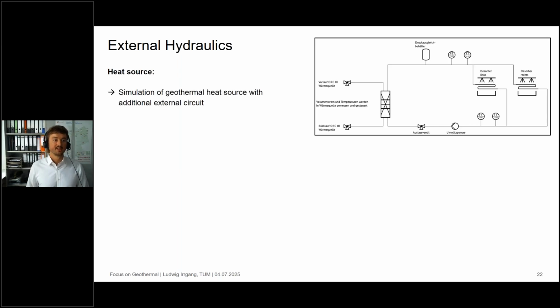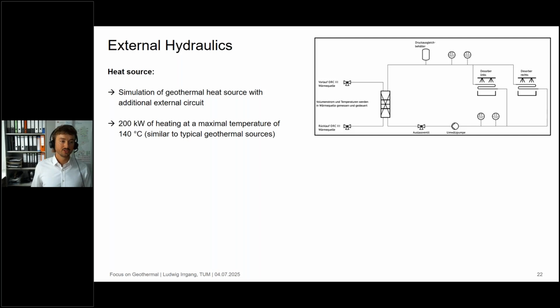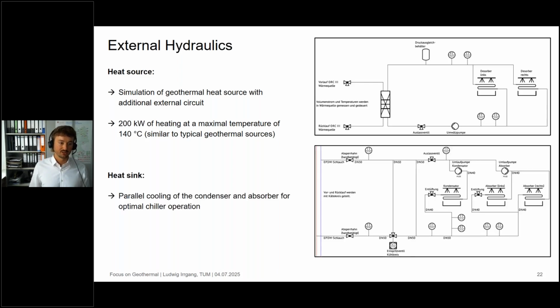For the external hydraulics, we simulate the geothermal heat source with an additional external circuit. So we have the heat source and then another circuit. This way we want to simulate different desorber temperatures with different geothermal source temperatures and find optimums, because it's always a trade-off between how far we cool down the geothermal brine and how the absorption heat pump generates. We have 200 kilowatts of heating at a maximum temperature of 140 degrees, which can simulate the boundary conditions of a typical geothermal project very well. For the heat sink, we designed parallel cooling of condenser and absorber for optimal chiller operation, but also mainly because we want to prepare for the heat pump and heat transformer operation.